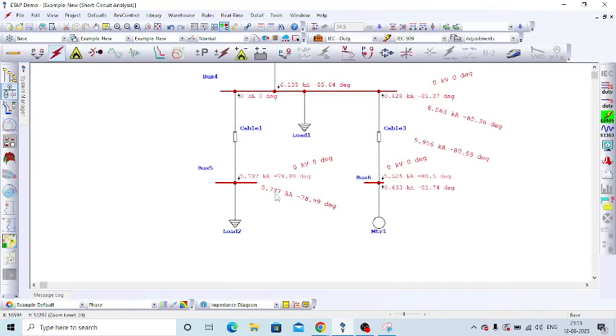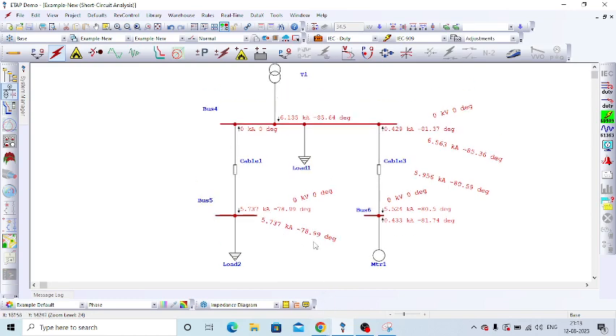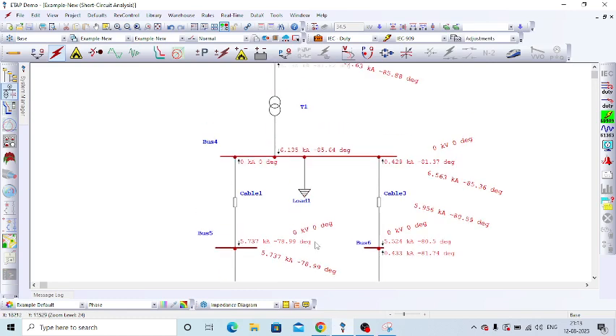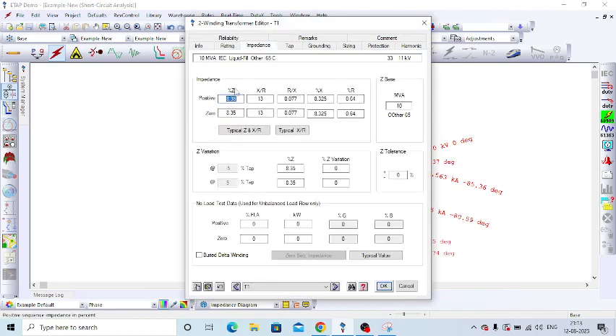Now it is 5.737. So a small amount of fault current reduction has happened, but not that much. So in order to reduce the fault current further, we have some other options. There are multiple options. One option is to increase the impedance of the transformer. Presently it is 8.35. So for just one calculation purpose, I'm going to increase it to 9.35.